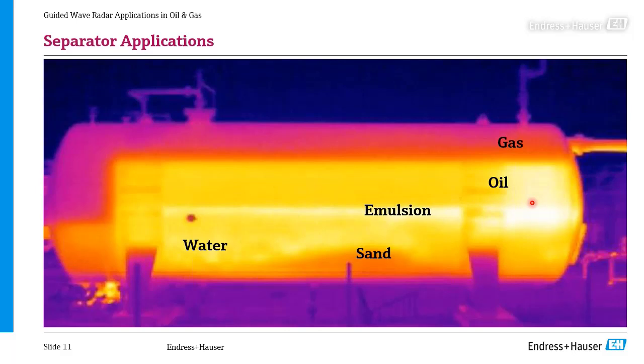And why do you need those instrumentation on top of it? Well, on the right-hand side, where the oil is, you want to measure the amount of oil that comes out of it, and make sure that the oil is not flowing back into what came in of it. And on the other side of the weir, you want to know how much is in there, and you want to make sure that also the water is not going over the weir into the oil section. Now, if you also want to measure the sand, and maybe also want to measure the emulsion on a continuous basis, I think guided wave is probably not the right technology to do so.